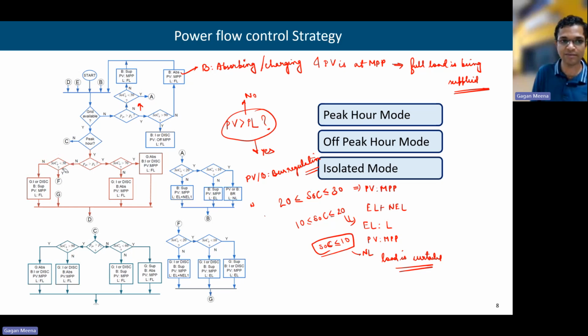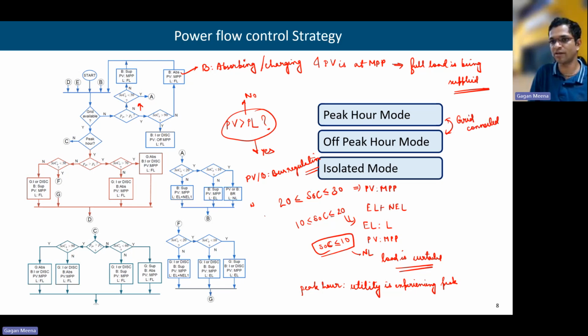If SOC is less than 30%, yes, then because it's a peak hour from the utility side, when we are talking about peak hour here, the utility is experiencing the peak. That's why the peak hour and off-peak hour modes are concerned with only the grid-connected mode, because here we are talking about the peak of the utility, not the microgrid. That's why these two are for grid-connected and this is for the islanded or isolated mode. Peak hour, the utility is experiencing the peak here.